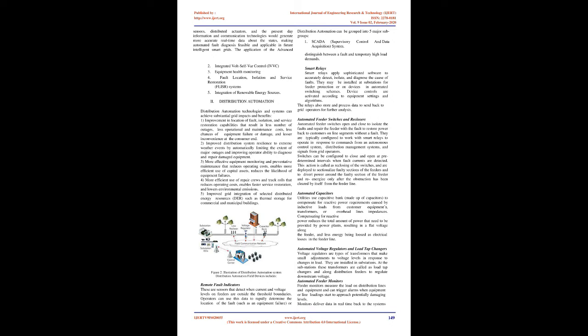buildings. Distribution automation field devices include remote fault indicators. These are sensors that detect when current and voltage levels on feeders are outside the threshold boundaries. Operators can use this data to rapidly determine the location of the fault, such as an equipment failure, or distinguish between a fault and temporary high load demands. Smart relays. Smart relays apply sophisticated software to accurately detect, isolate, and diagnose the cause of faults. They may be installed at substations for feeder protection or on devices in automated switching schemes. Device controls are activated according to equipment settings and algorithms. The relays also store and process data to send back to grid operators for further analysis.